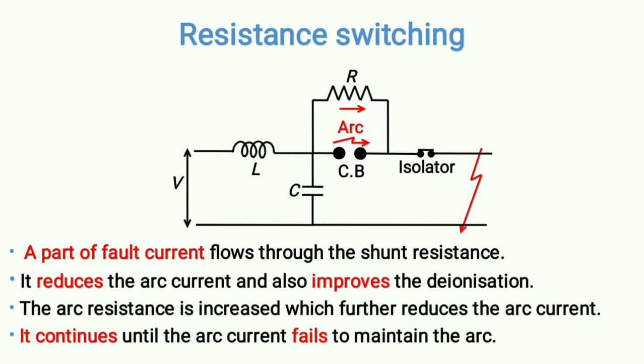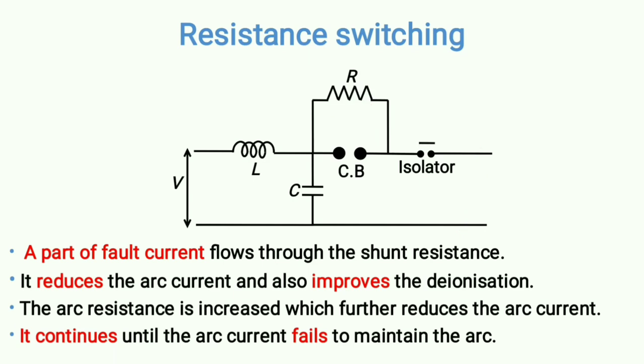The cycle continues until the arc current is too low to maintain the arc, and the arc is completely vanished. At that point, the entire current flows through the shunt resistance and the circuit breaker contacts are separated with no arcing. However, fault current is still flowing through the resistance, so we use an external isolator to disconnect it, completely eliminating the fault. This is how resistance switching prevents current chopping.